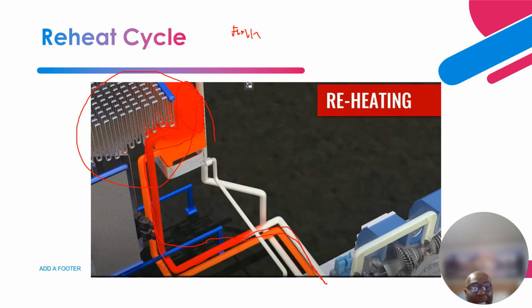So that flue gas is fed around this piping, and the steam gains that energy from the piping to increase its temperature, to get it ready for the next section of the steam turbine, that is the intermediate pressure section. Once it completes the intermediate pressure section, it goes through this crossover and into the low pressure section before the steam comes down and collapses into the condenser.